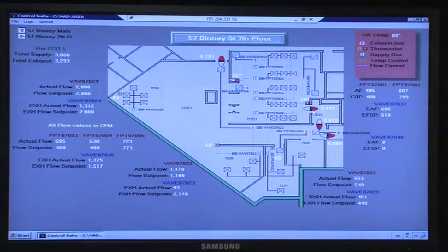And those all have to be 0.05. Nuke medicine, second floor, a high differential. Alright. Outside that fume room, the radiation room on nuke medicine. Is that right? I said it right. Okay. We could not come up with a way to monitor those 2 doors. Those are the swinging stainless doors with the rubber grommets, or gaskets, and they're not sealed tight either.